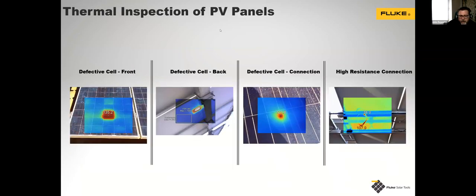When we're looking through a thermal imaging camera, it's quite interesting in that solar panels don't really want to get hot. What we really need them to do is transfer that energy and make it into electricity. If you see heat on a solar panel, that's usually not a good thing, or at least an area of concern. So you're looking at some examples here. We've got a defective cell from the front, the back. We've got a connection issue here, and also we've got high resistance connections in the cabling that comes out of the back. So all of this can be very quickly checked.